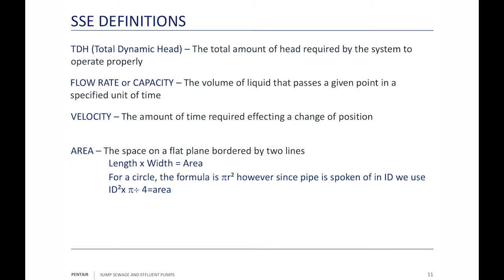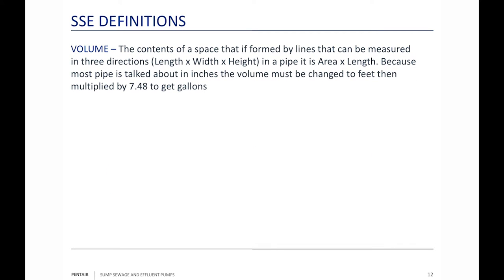Volume is the contents of a space measured in three directions. For a leach field, that's length times width times depth. For a piping system, it's area times length, giving cubic inches; divide by 1,728 to get cubic feet, then multiply by 7.48 to get gallons. Atmospheric pressure is the weight of the atmosphere at a given point and time — it changes. Vacuum is the measure of a pressure below atmospheric pressure — not necessarily the void of outer space, but something less than atmospheric pressure.